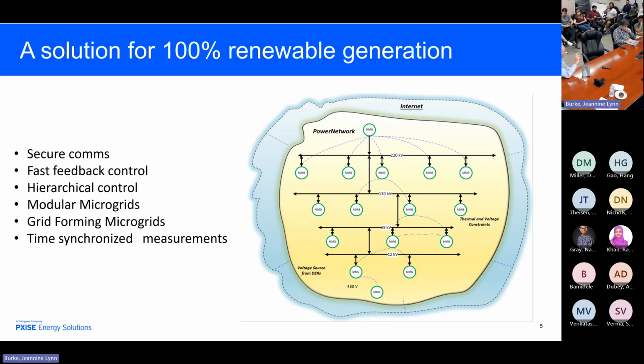This is extremely important in control, to use time synchronized measurements. The reason being, when we do a control calculation, as you all know, you get a measurement, you have a set point, you calculate the error. Your set point value and your measurement should be at the same time. In a SCADA system, they can be off by 4 or 5 seconds or 15 seconds.